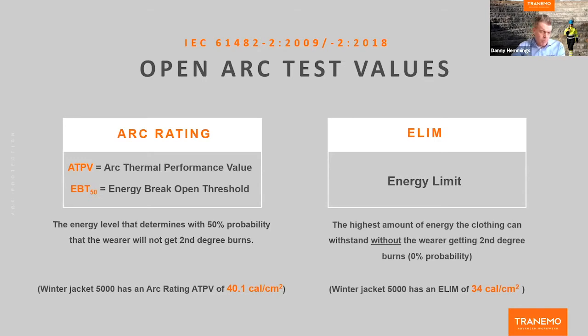There's an example there at the bottom with a Tranemo winter jacket, flame retardant arc winter jacket, which currently has an ATPV rating of just over 40 cal. On ELIM, that's reduced to 34 cal. So it's not a like-for-like reduction. Even though we're going from 50% probability to 0% probability, you're, in that scenario, losing approximately 15%. But that reduction of 15% now gives you a 0% probability. In time, everything will move towards ELIM and 0% probability.